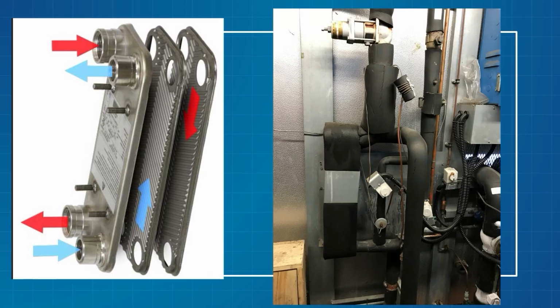The other little bit, and I could probably do 4 hours on this heat exchanger, I really find it fascinating. I know you don't. So let's speed through this. The other piece I do want you to notice is that it's counterflow. That means my primary side is flowing that way and the secondary side is flowing that way. Why do we do that? The reason is the coldest spot on this entire thing is right after my TXV. Well, that's right here. The warmest refrigerant I've got on this whole thing is this secondary refrigerant coming in.